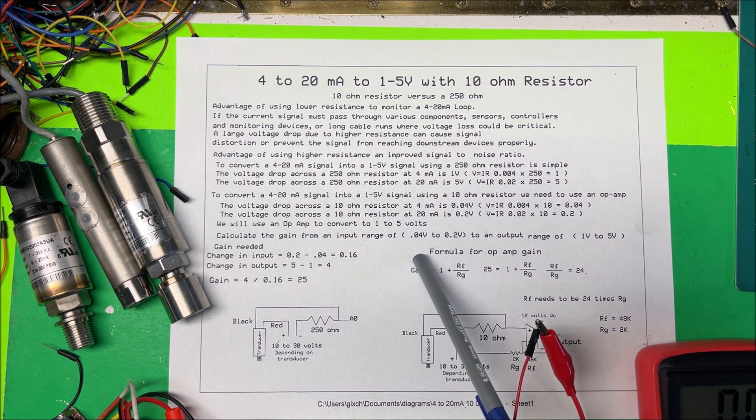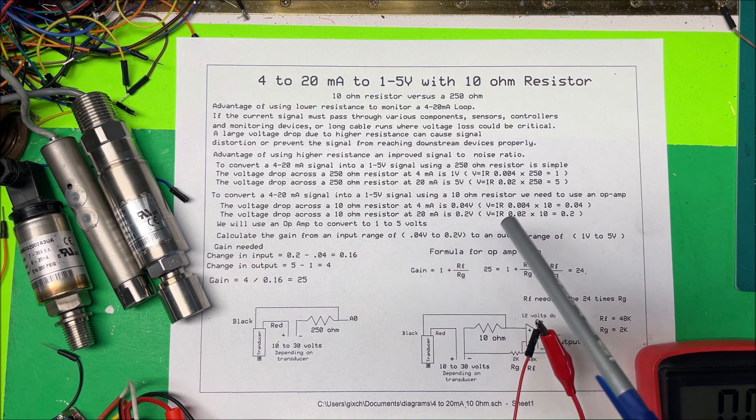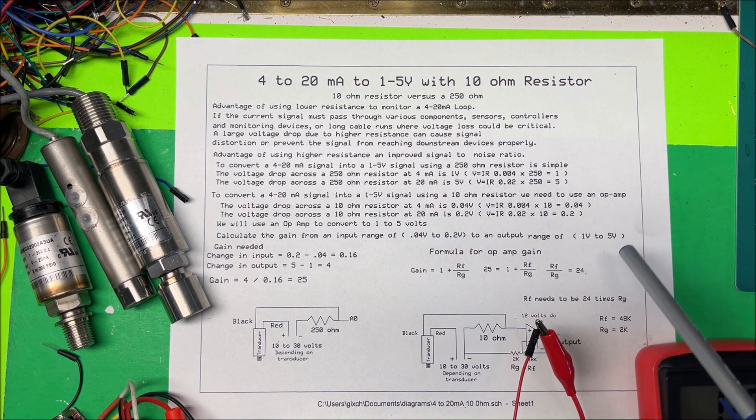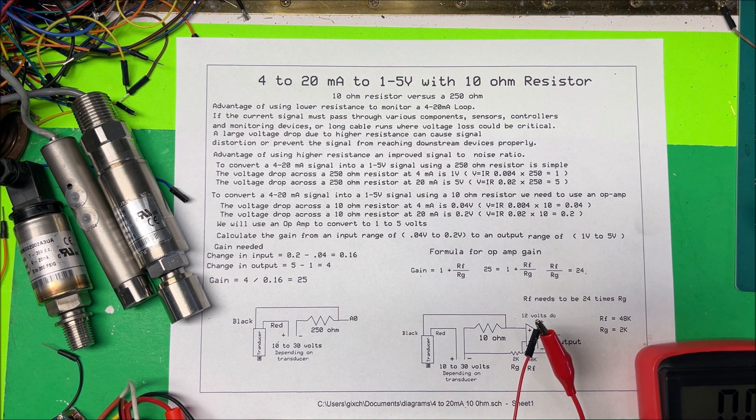So what we're going to do now is we have to find out the gain. We're going to just have to use an op amp to bring that back up to the 1 to 5 volts, so we need to find the gain of the op amp we need. The change in input voltage is from 0.2 to 0.04, so that's 0.16 volts difference. The change in the output is 5 minus 1.